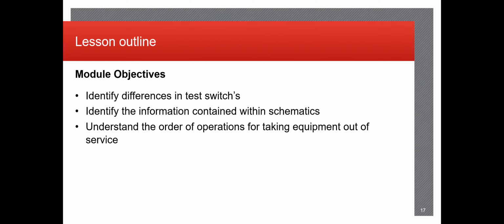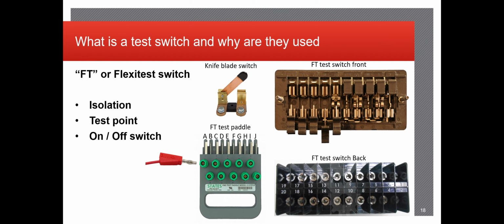So in this portion of the slideshow, we're going to be going over some of the smaller equipment, for example, the test switches, any of those little pieces of information contained within the schematics, and specifically in this case, understanding the order of operations for taking equipment out of service. So these are a few common examples of test switches. They are primarily used for isolation purposes, meaning that usually a relay that is in service will have wiring running out of the relay directly to test switches.